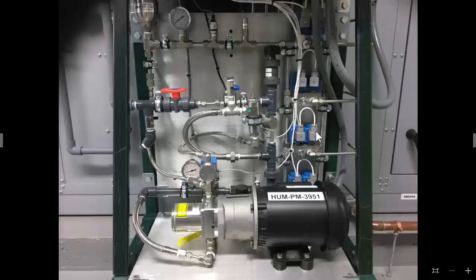Well, if you called for a particular zone, this is zone 3, and it's stuck closed, the processor would say, hey, we're still not getting capacity. Let's go to zone 4 here and turn that on, and then it would get its capacity and catch up, and then it would say go back to zone 3, and it wouldn't come on. So actually it would run fine if this was stuck closed, but we wouldn't get very good capacity control. So I think that's it, running through the different variations of what happened if we had some zone control failures.